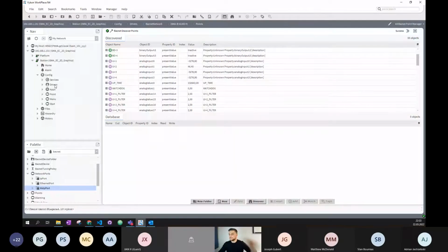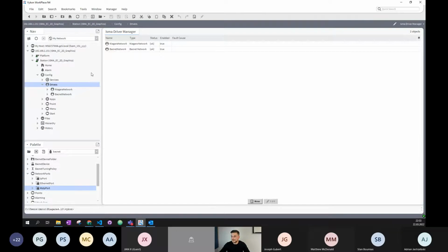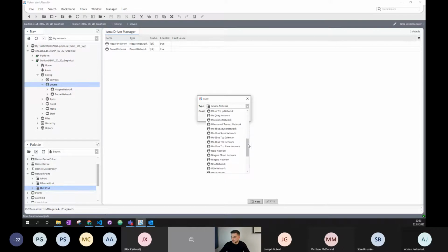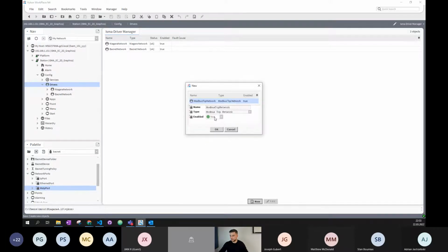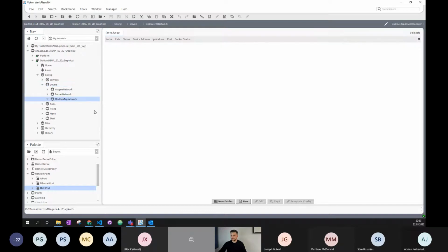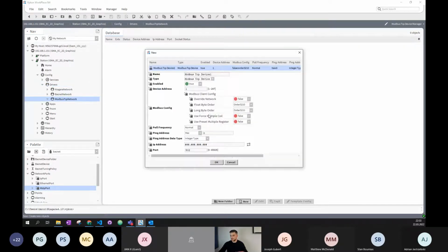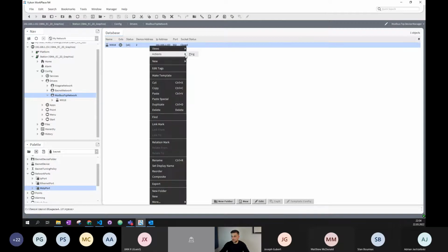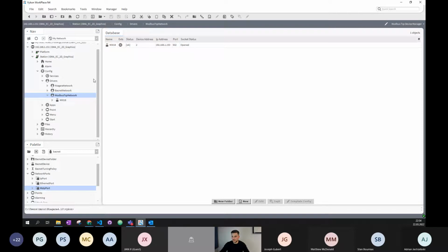And right now, let's just go back to my Niagara. And I will just show you how to make use of it. So right now, I'm going to use the Modbus TCP network. Of course, we have a network, then we can add a new device. First device will be my Mix18, which has device address 2 and an IP address of 192.168.1.153. So this is the device which has the IP Ethernet port. So there are no issues. We can ping it. No worries. Everything's working like a charm.